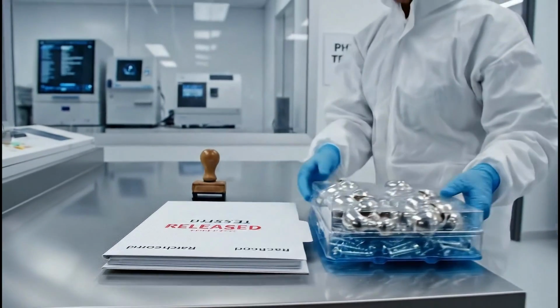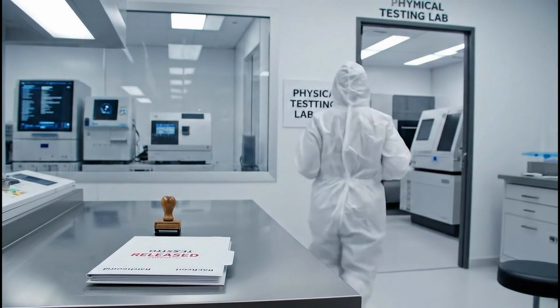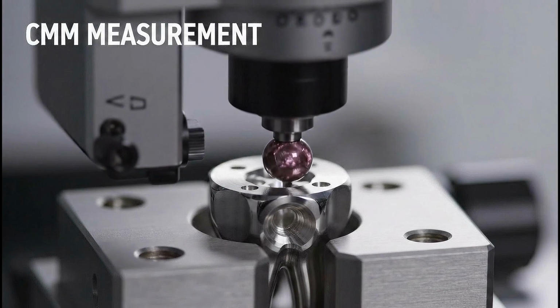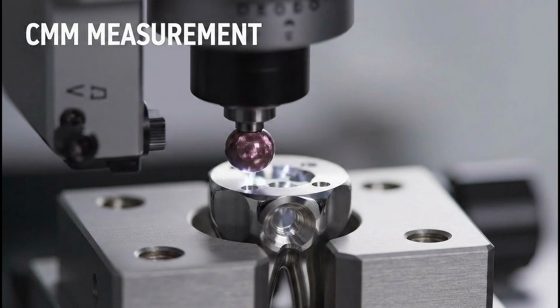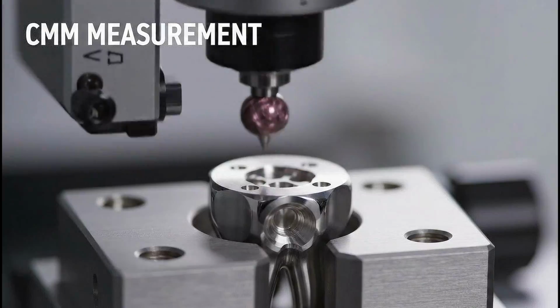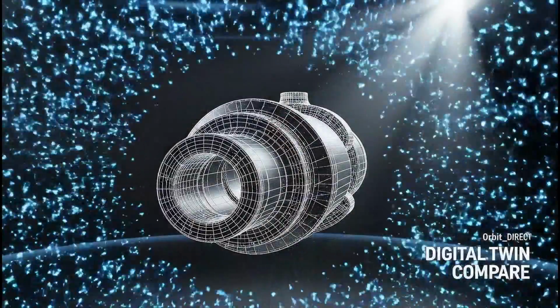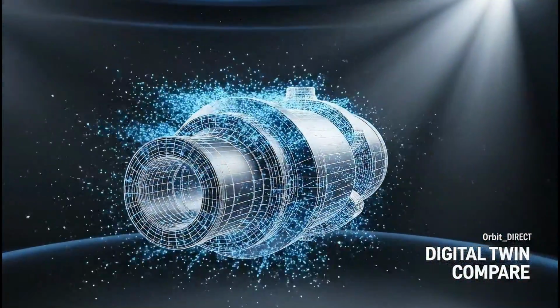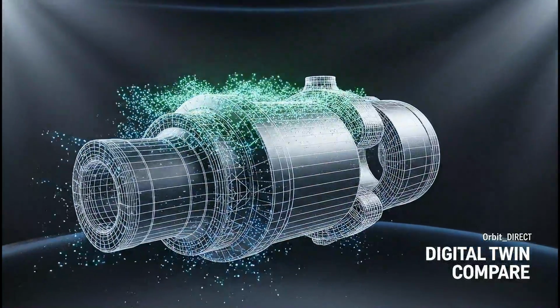Now we move to physical testing, where we push the metal to its absolute limits. A coordinate measuring machine verifies the internal hex geometry. This shape transfers the torque during surgery. The physical part is compared against the digital twin. Tolerances here are measured in microns.